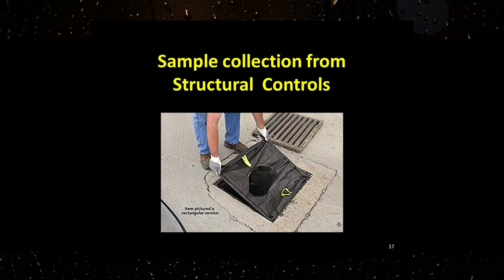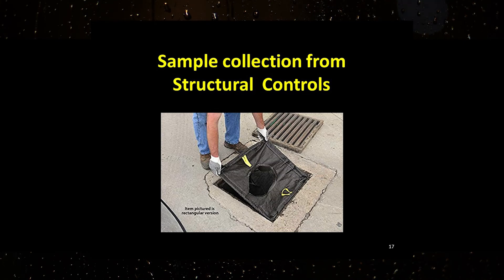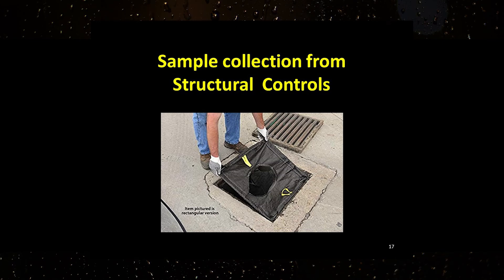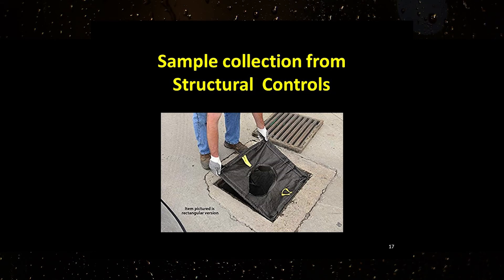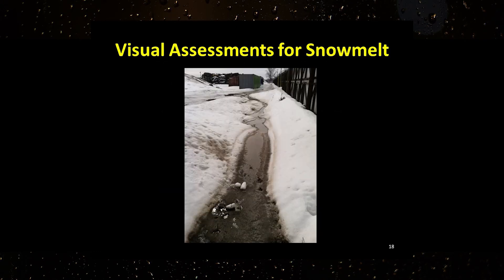Structural controls may be in place to remove contaminants from the stormwater runoff. The stormwater sample should be collected after the stormwater has passed through the structural control for assessment of the stormwater discharging from the facility. In these situations, sample collection will be more difficult and specialized equipment may be needed — this information should be included in the written procedures. Collection of a sample from a snow melt event must be during a period of measurable discharge; basically, there must be flowing meltwater.